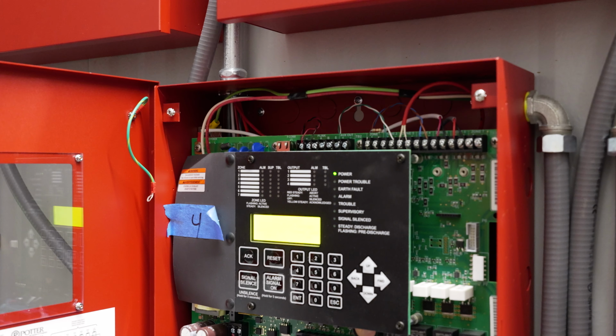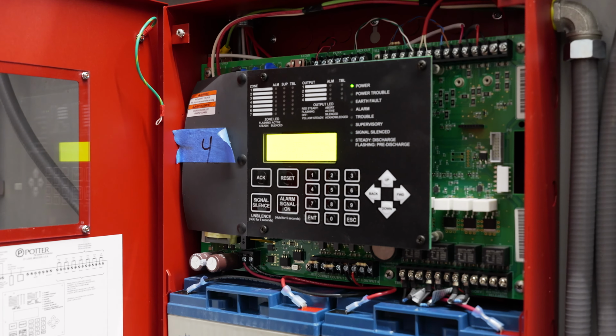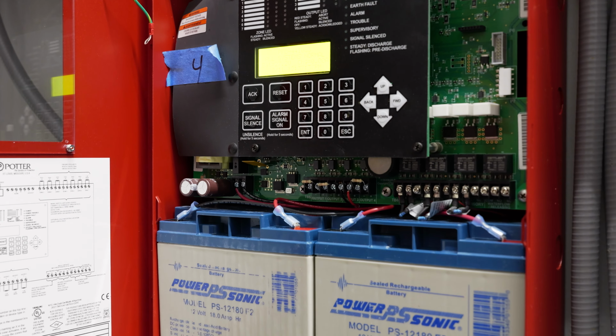The releasing panel contains backup batteries that, in the case of a power interruption, will ensure normal system operation. The last item on the trim that I want to mention is a pressure alarm switch. This switch will send an alarm signal to the building fire alarm panel if a system is manually activated and in the case of normal operation is redundant to other releasing panel alarm functions.